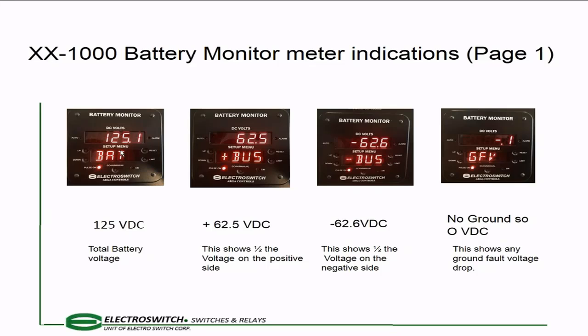So standard condition, you're at 125 volts. This is your battery; you're monitoring the battery. If I push my little scan button, which is right here in the center on the bottom, underneath the feature that you're monitoring, then I'll switch to the next positive DC bus, then the negative DC bus, which is half the voltage. If you had a ground, it would show you a ground. In this case you don't have any ground, so it would indicate a positive ground or a negative ground. I could hold that scan button down, and it can be automatic scanning or just individual pushes to switch between them. If I hold it down for about 4 seconds, it goes into an automatic phase, which is a nice thing. I could walk into a substation with a panel-mounted unit and quickly see the status of my battery.